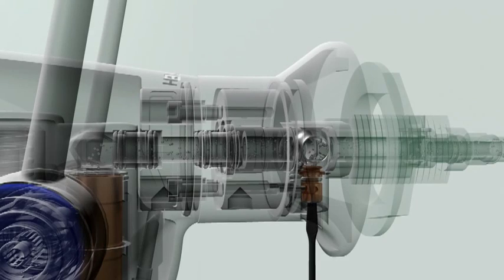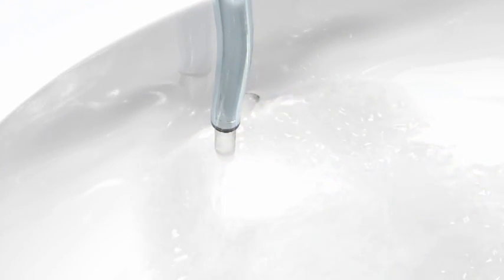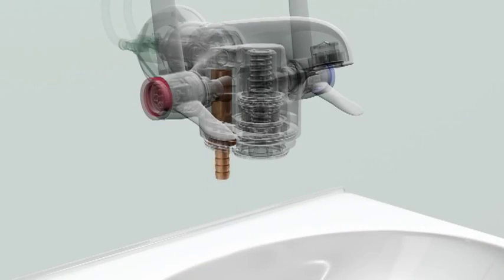When the water runs clear, isolate the cold water supply at the spigot. Remove the flushing adapter and replace the strainer and check valve cartridge. Repeat this procedure for flushing the hot water supply pipework, taking care to avoid scalding. The flushing adapters can also be used for hot and cold water supply sample collection and to check the temperature of the water supplies.